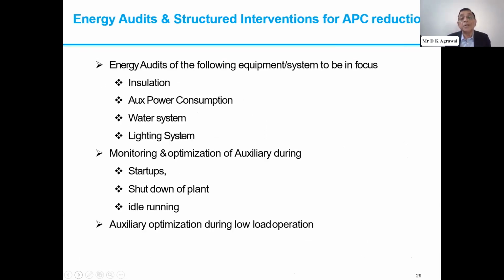So energy audit is also very much needed. I am sure many utilities must be doing this: insulation audit, auxiliary power audit. And for auxiliary power, we strongly recommend that an energy efficiency management system should be put in place, because when we are talking about partial loading and there is so much crisis in such a competitive scenario, this energy management system must be there.